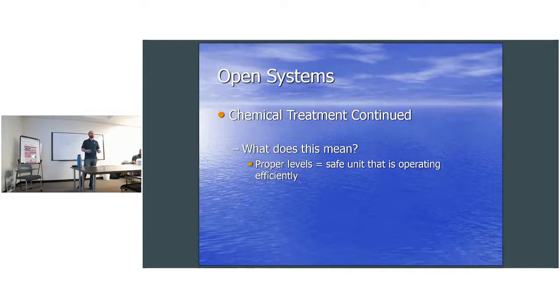No, but I thought it was, yeah, sorry to interrupt, but when you guys were in Seattle talking about steam boilers, about treating the steam, because the chemicals actually go into the steam and then up through the pipes. They can. If you over-treat a steam boiler, you can get carryover. So you can actually carry the chemical in the steam. So if you're in a food plant, you have to be really careful about what chemicals you use.